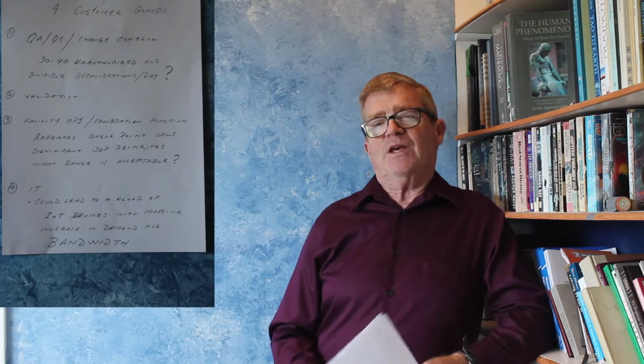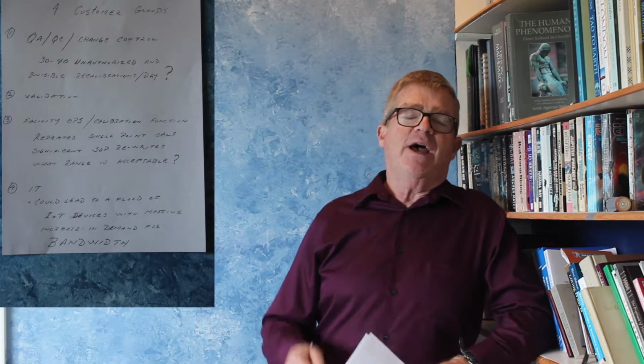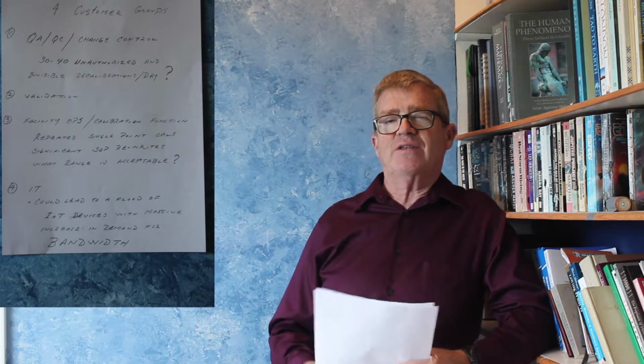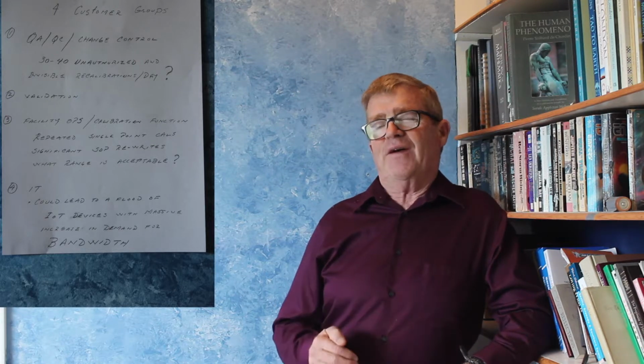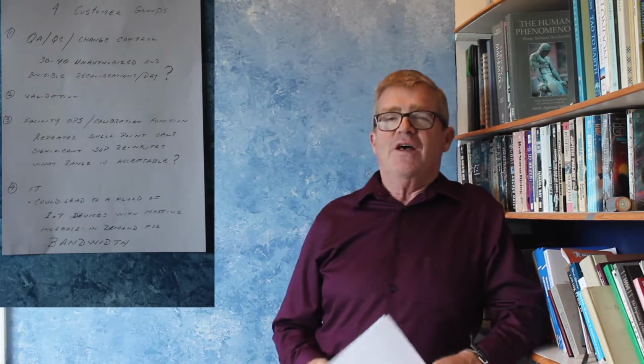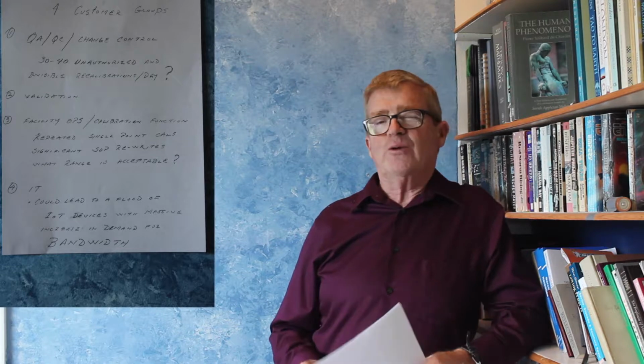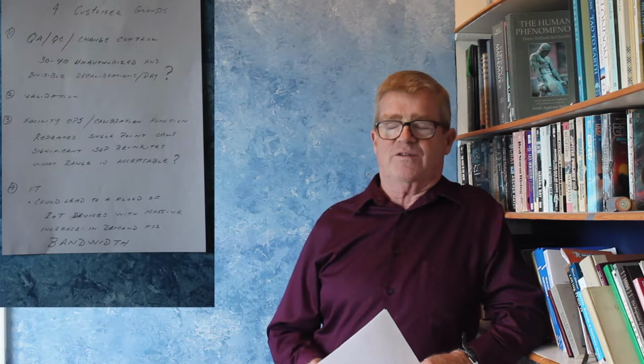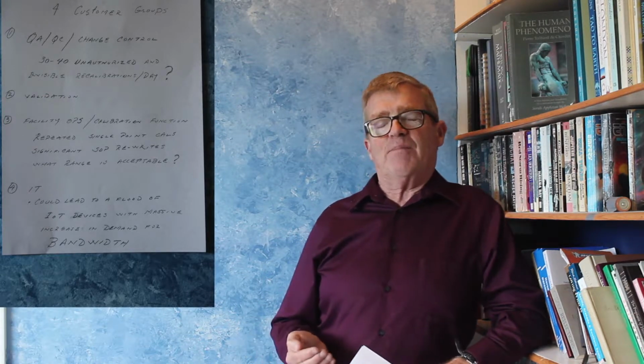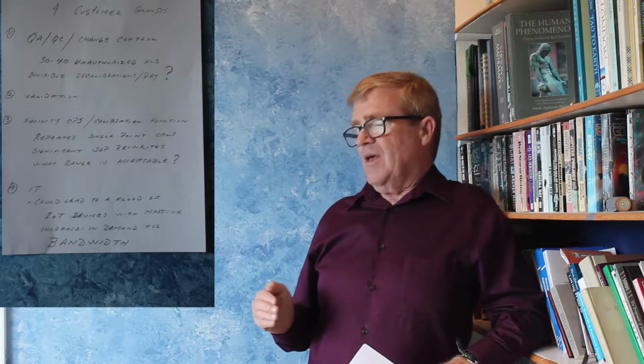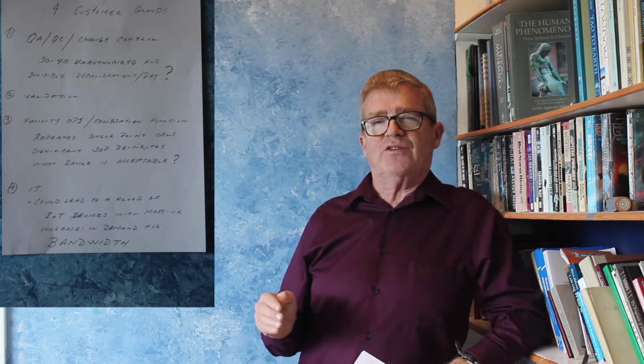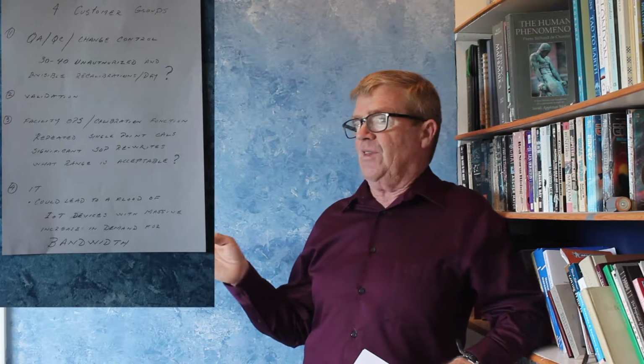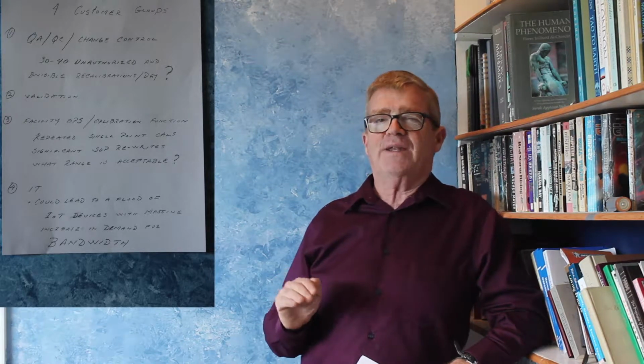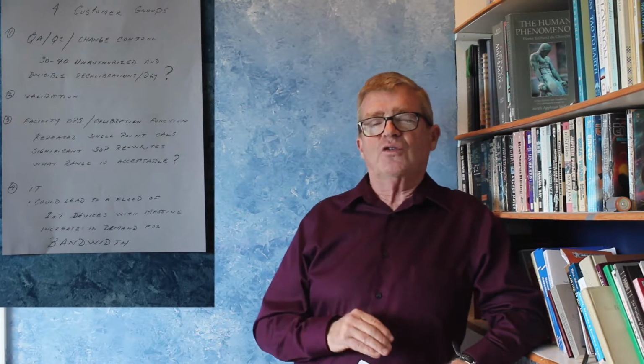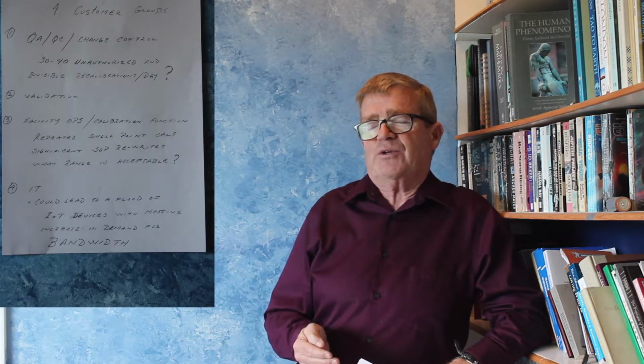Next group at the table is the group that's closest to my heart, and that's the facility operations guys and the calibrators. At the very least, if we buy this device, there's going to be a bunch of calibrators rewriting a whole bunch of SOPs. And there's something going on in the background that's very interesting. Essentially, Endress and Hauser says a single point calibration for this device at a fairly high temperature will allow you to use it across a very wide range of temperatures.